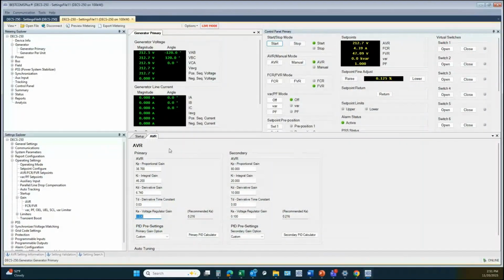So again, most commonly I recommend you use the auto tuning. It really works, but reduce the Ka value to something very low and then bump it up as you feel you need more of an aggressive response. The Ka value is a loop gain. It's essentially like a multiplier for all of the gains, similar to an analog stability pot on an analog AVR. As you increase it, it's going to get more aggressive. As you decrease it, it'll get less aggressive.